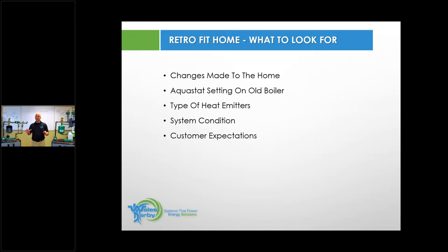Because if I don't pull that aquastat cover off, and I had a boiler set at 210, and I put a condensing product in there that may only max out, or some that max out at like 187 degrees, that's probably never going to work properly. So important to pull that off. Type of heat emitters again. Is it baseboard? I'm going to put a condensing product in there. Do I have the opportunity to make that boiler condense? You're selling them a system you want to be comfortable with. You're selling them a system that is going to be efficient. You want to make sure it will condense because there's value in the condensation.